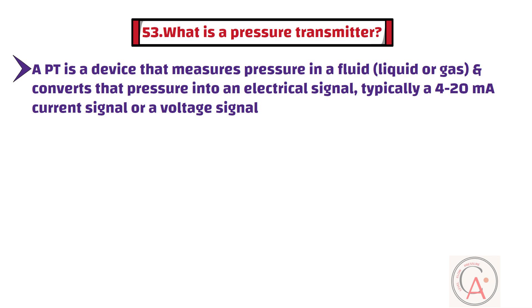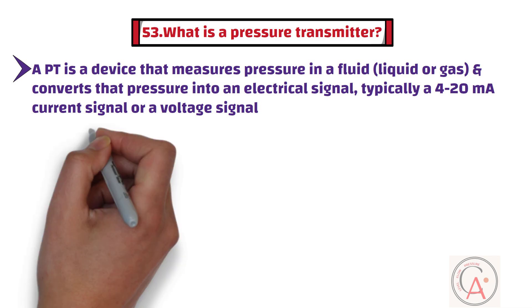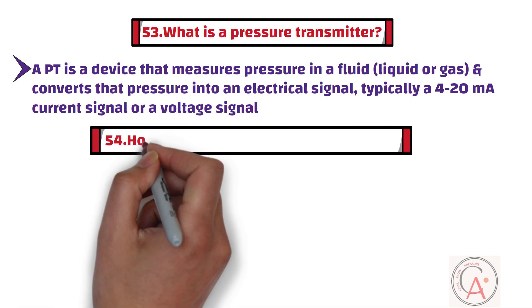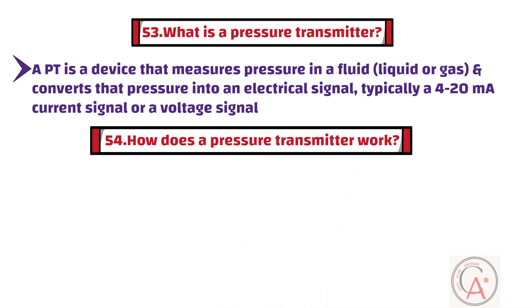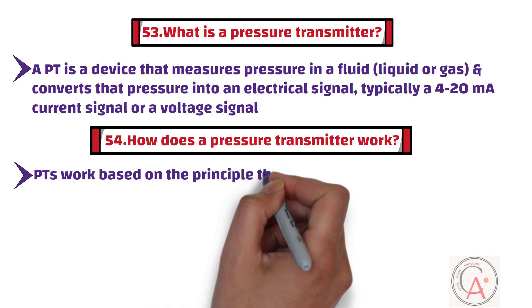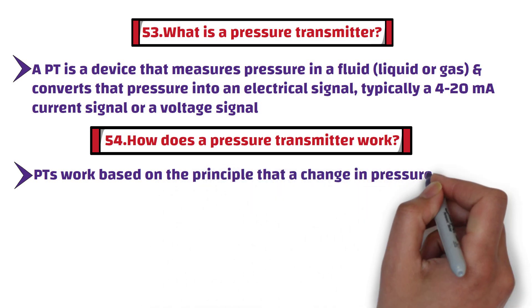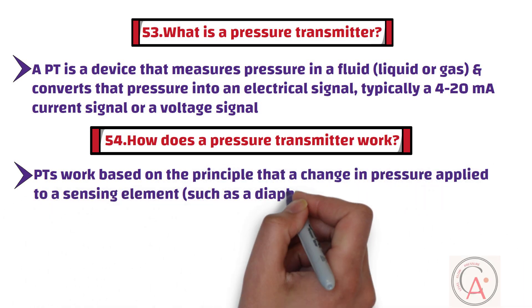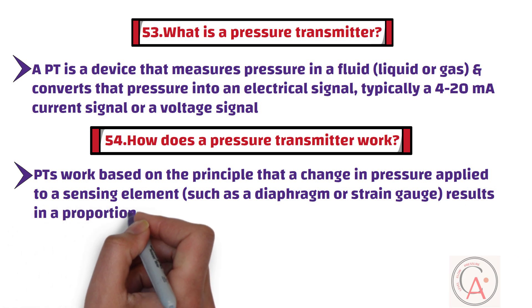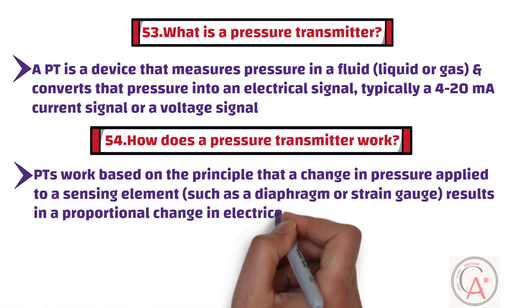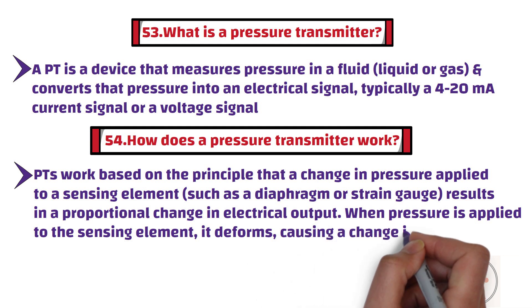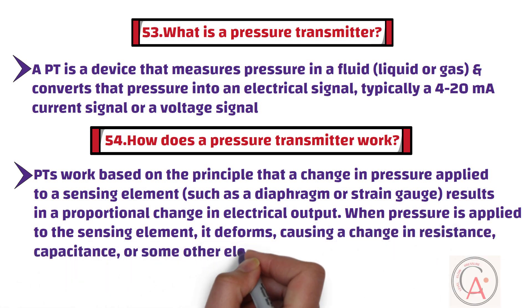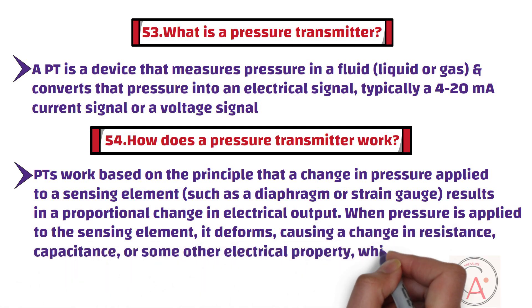Question 54: How does a pressure transmitter work? Pressure transmitters work based on the principle that a change in pressure applied to a sensing element — such as a diaphragm or strain gauge — results in a proportional change in electrical output. When pressure is applied to the sensing element, it deforms, causing a change in resistance, capacitance, or some other electrical property, which is then converted into an electrical signal that represents the pressure.